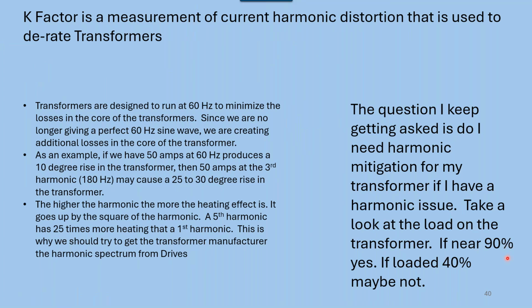If that transformer is 90% loaded, yeah, I probably need to get some kind of harmonic mitigation. If I'm 40% loaded, well, maybe that additional heat's not going to affect the system and I don't need it. I've got a job where the transformer's loaded 20%. My recommendation to the customer was, you don't need harmonic mitigation because you're so oversized to begin with. Of course, he chose to go ahead and put harmonic mitigation anyway, which is fine because I'll be glad to sell him the equipment. But my recommendation to him was, you don't need it.